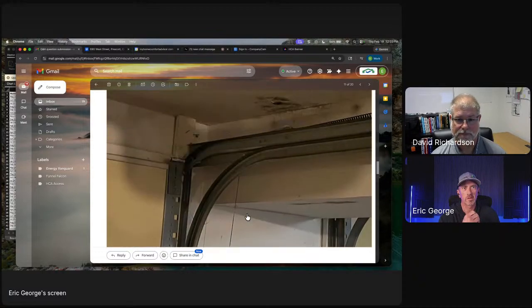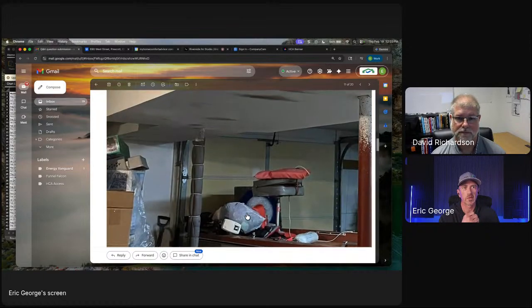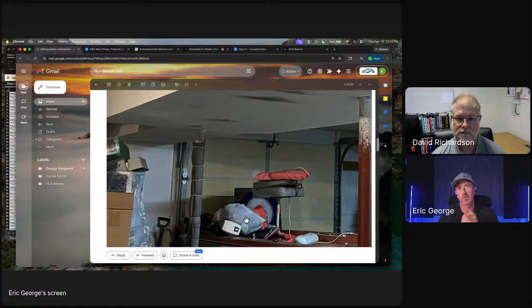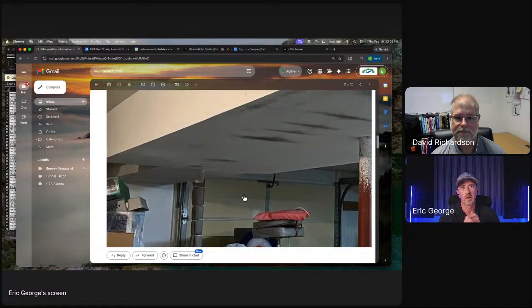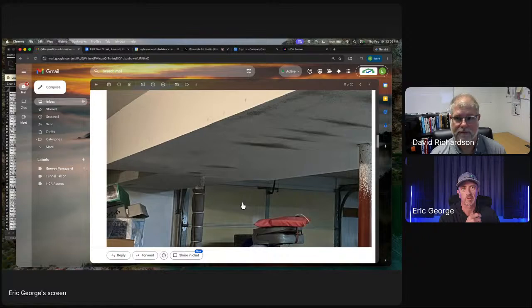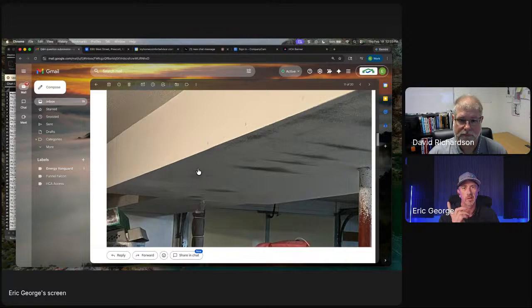That's kind of what I was thinking. I don't know how old the house is, he didn't tell me that, but I'm guessing it's at least 20 to 30 years old, maybe older. The ductwork may not be insulated at all in that case. So if you've got a main supply trunk line going through the garage like that, feeding a room above, and it's not insulated at all, it's definitely going to sweat. The hotter you make that garage, depending on what the air temperature is, no matter really what the air temperature is, typically the air coming out of an HVAC system is in the 50s, mid 50s or so.